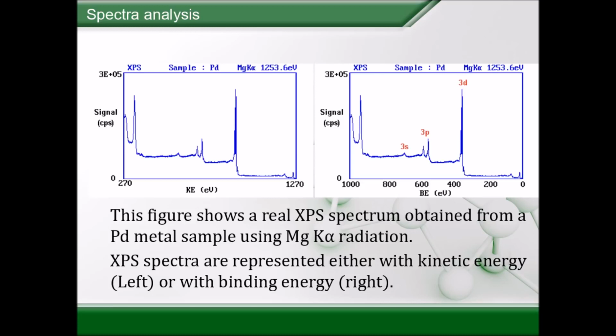A photoelectron spectrum is recorded by counting ejected electrons over a range of electron kinetic energies. Peaks appear in the spectrum from atoms emitting electrons of a particular characteristic energy. The energies and intensities of the photoelectron peaks enable identification and quantification of all surface elements. This allows elements on the surface to be identified based on the unique binding energy each element has.